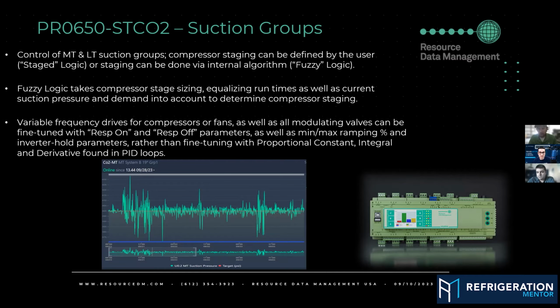They shouldn't be touched, because you guys fine tune them with the OEM or with the manufacturer of the equipment. So when it gets out to the field, the technician, the control guy, should be able to install it and not have to play around with it. But that's why there's commissioning and startup. Maybe there is a little bit of fine tuning that those guys that understand controls need to change a little bit. Is that correct? Yeah, exactly.